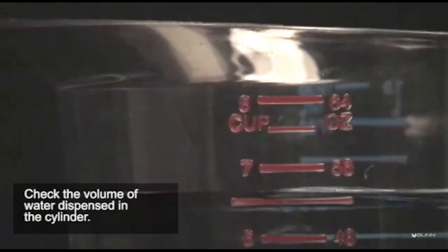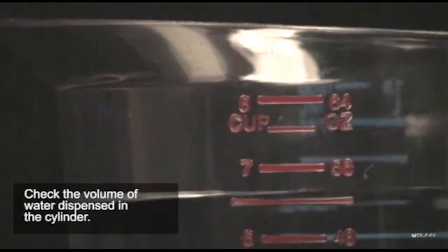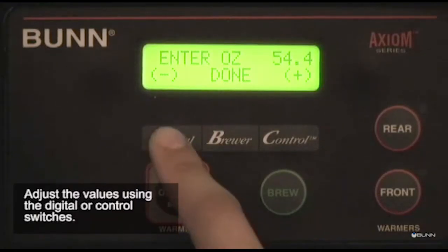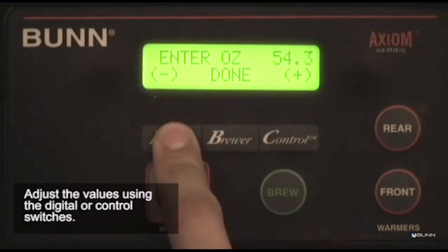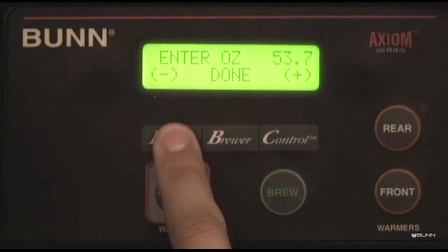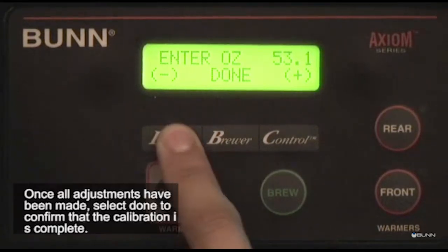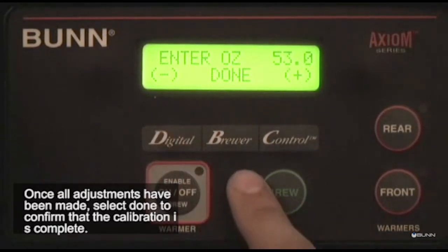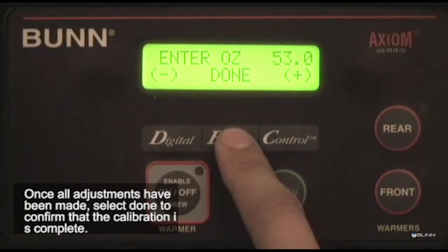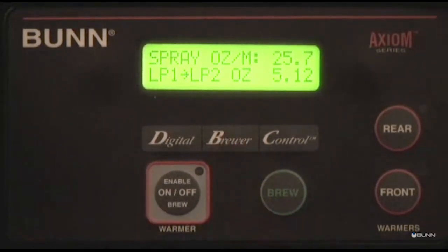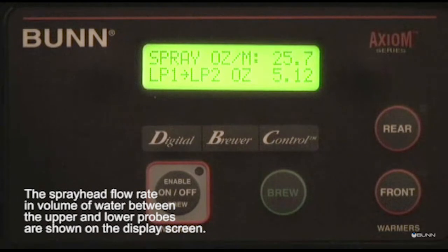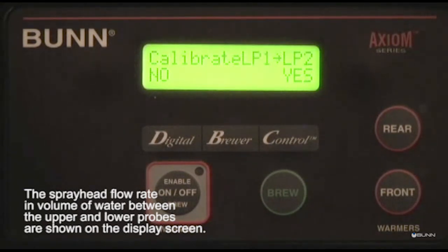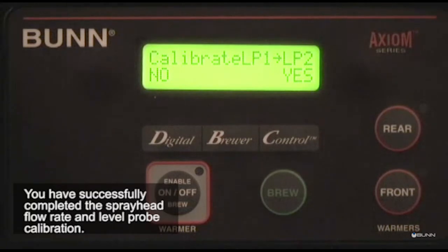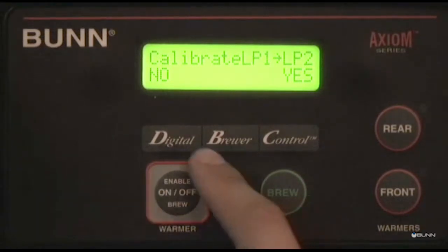Check the volume of water dispensed in the cylinder. Adjust the values using the digital or control switches. Once all adjustments have been made, select Done to confirm that the calibration is complete. The spray head flow rate and volume of water between the upper and lower probes are shown on the display screen. You have successfully completed the spray head flow rate and level probe calibration.